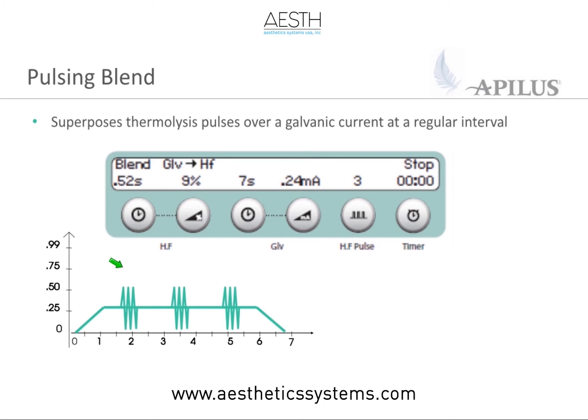When we talk about the blend methods on this machine, we have two basic types of blends. One is a pulsing blend and the other is a continuous blend. This first one here, you'll see the blend method, you'll see which one your lead is, and you will see a number here that will denote how many pulses of high frequency. This is a pulsing blend.